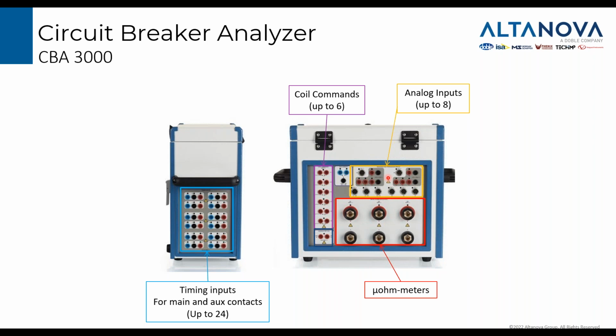For example, you may want to measure the voltage from a current clamp, or measure the voltage during a resistance measurement. The voltage is a voltage drop that is generated by the current flowing into the contact, and the current can be generated. So the CBA 3000 can generate at the same time 3 independent currents up to 200 amps.